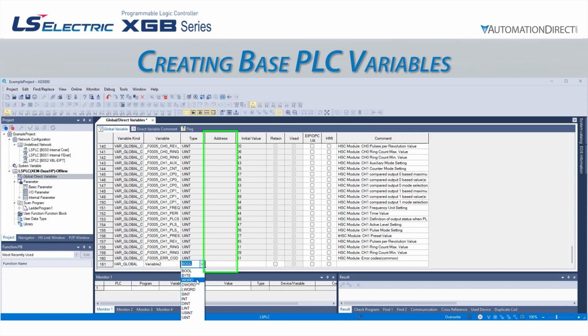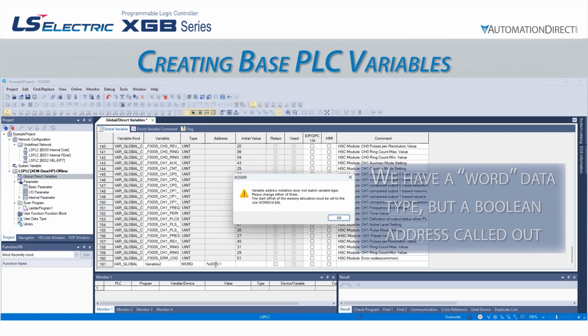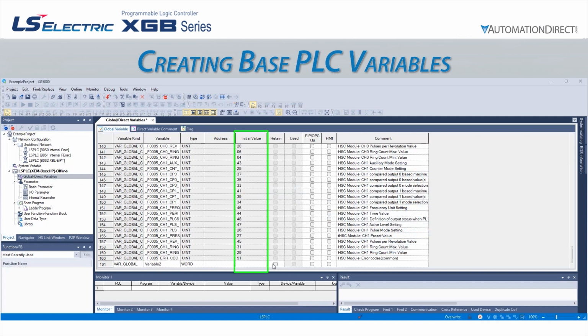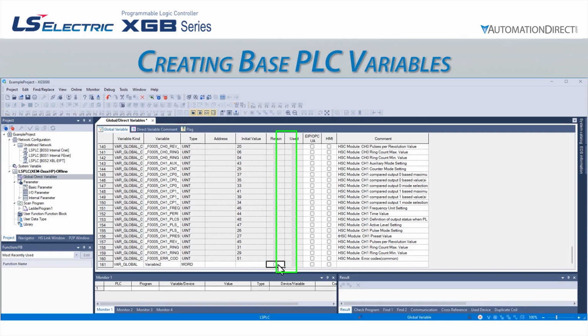The address column can be used to tie this global variable to a specific direct variable. If we select an address for a different variable type than we have selected, the software will give us an error message. The initial value column can be used to control the value of the variable when the PLC starts scanning. The retained column determines whether a variable value will be retained through power loss. The used column indicates if the variable is used anywhere in the project.